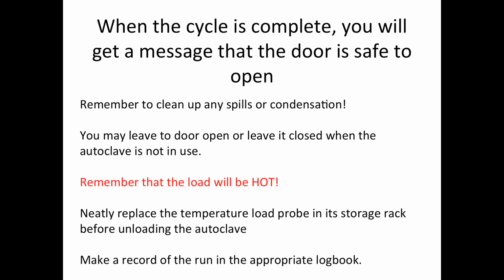Remember to clean up any spills or condensation. You may leave the door open or leave it closed when the autoclave is not in use. We have no official policy on that point. Remember that the load you're taking out is going to be hot. If you've used the load probe, you're going to neatly coil it on the little storage rack on the side of the autoclave and make a record of the run in the appropriate logbook.